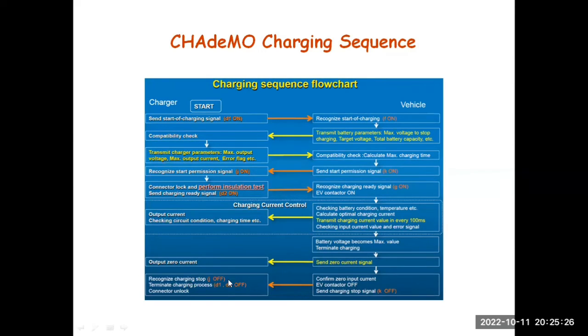Once the current becomes zero, the EV contactor goes off and sends the charging stop signal, removing the charge enabled signal. The charger recognizes the charging stop and terminates the charging process, and the connector lock gets unlocked. So this is one charge cycle.